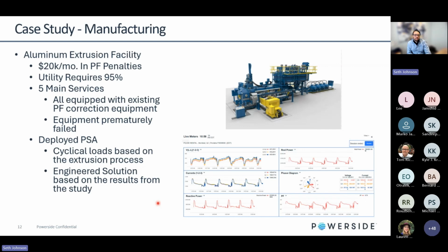a year span. There were 5 main services in this facility, and all of these services were equipped with existing power factor correction equipment. Although I don't get out in the field quite as much as I used to, I was fortunate enough to go to this facility and look at it. One of the things I noticed was that all of the power factor correction equipment had failed. Now, of course, it's a dirty environment, it's manufacturing, but I was a little surprised that they failed so quickly, given the age of some of the equipment.